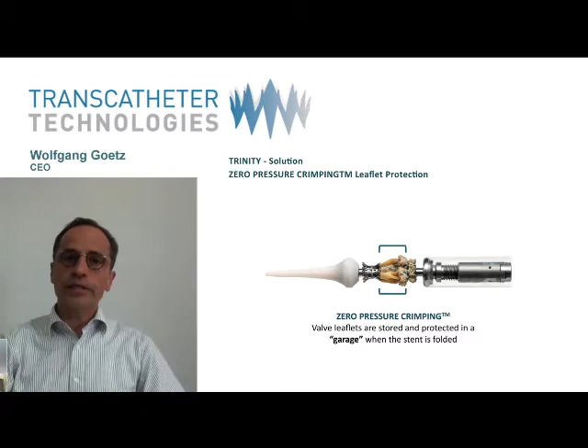The Trinity catheter is inserted over the apex of the heart. When the sheath is retracted, the valve remains folded here on the left side of the slide. Then the valve is positioned and slowly and stepwise expanded and anchored. Now, the valve function can be fully evaluated. If the result is not acceptable, the valve can be refolded here on the left and repositioned. If the result is acceptable, the valve is released here on the right. It is important that there is no more change in geometry when the valve is released. The valve remains exactly the same as when it was evaluated.